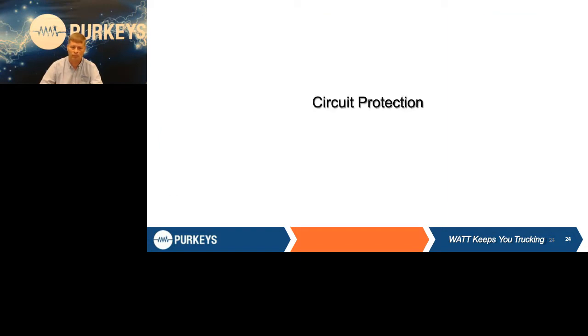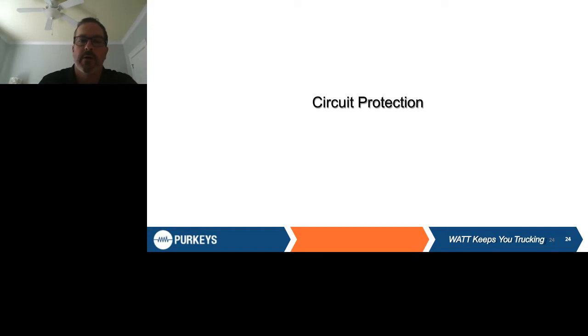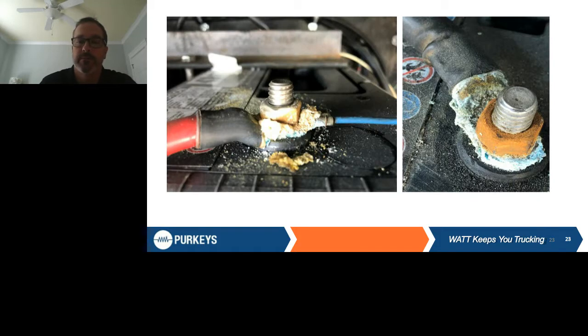Larry, if I could say something about that last picture as well. You see right there, while corroded, it is seated properly. You always want to have the largest terminal on the bottom and stack them largest to smallest, because you want the greatest amount of surface space to conduct that electricity. But we commonly see the smallest ones on the bottom, the largest somewhere in the middle, and another small one on top. Stack them from the bottom, largest to smallest.